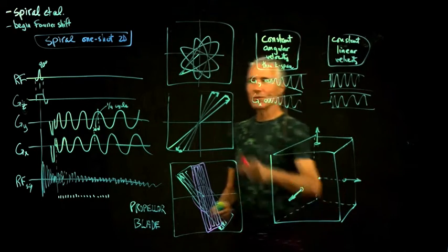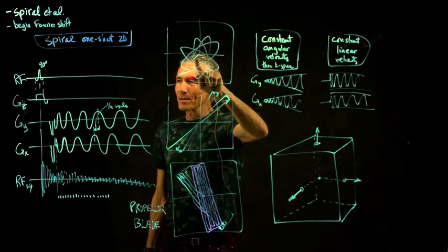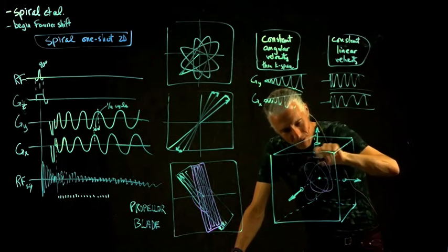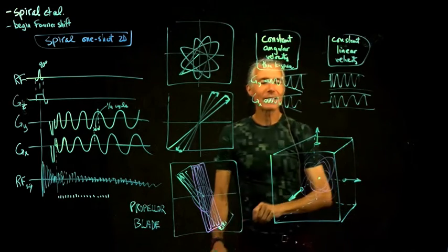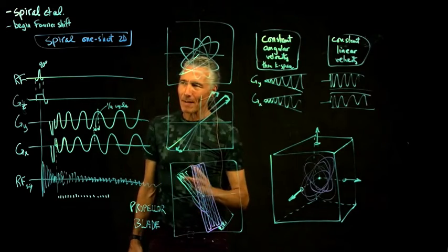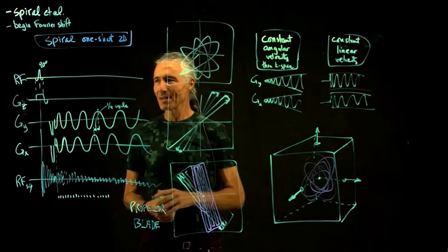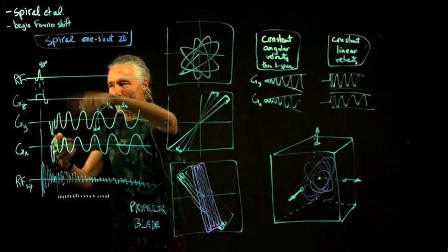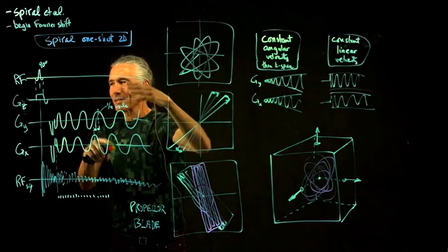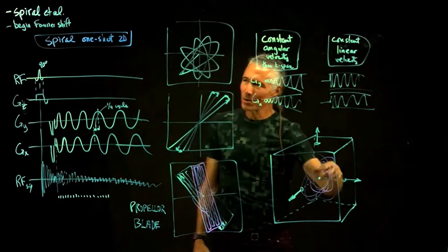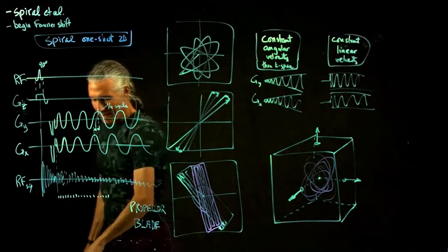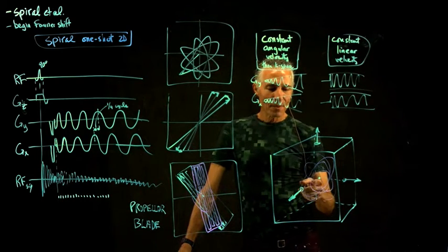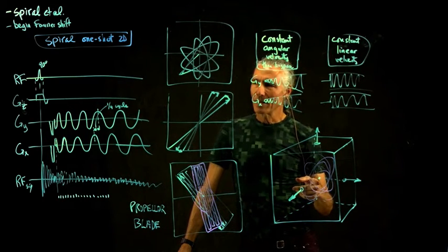And then what you do is you just do this kind of thing, except do it in 3D. So you would imagine you're kind of rotating around in three-dimensional K-space. This is like the absolute optimal super fast method of collecting data, because you got all three gradients on. So basically you would turn on all three gradients and they'd all be oscillating at the same time to run you through K-space like that. And people did this once. They actually showed that it could work, but this would be the absolute fastest way of collecting 3D K-space.